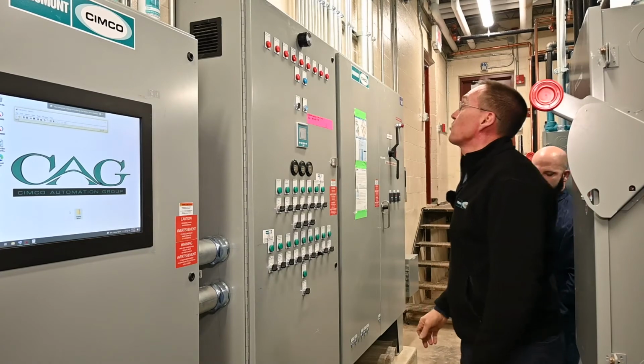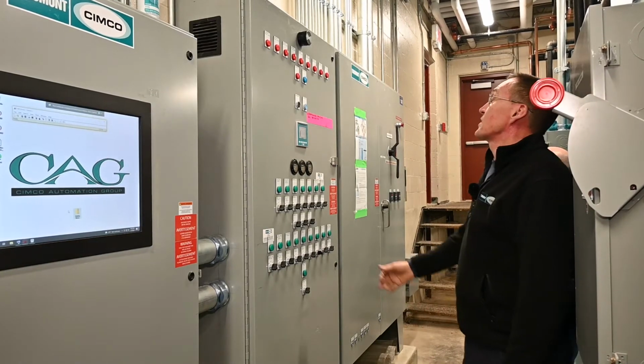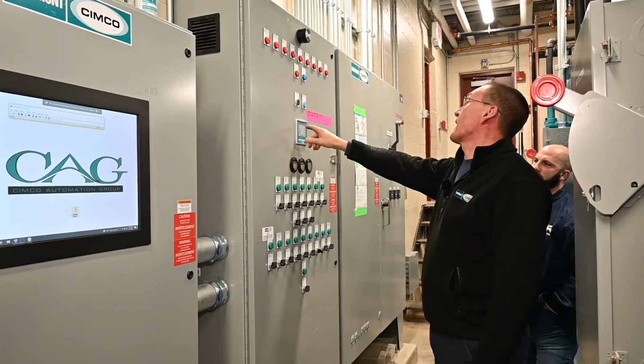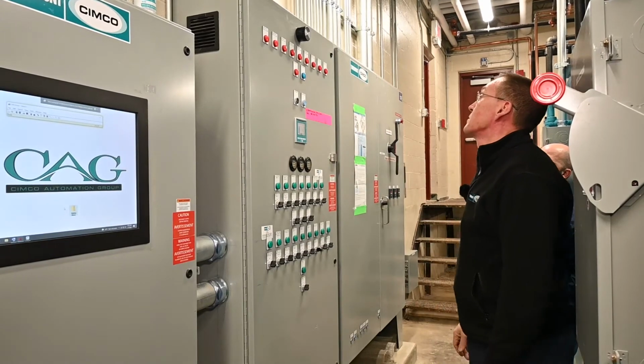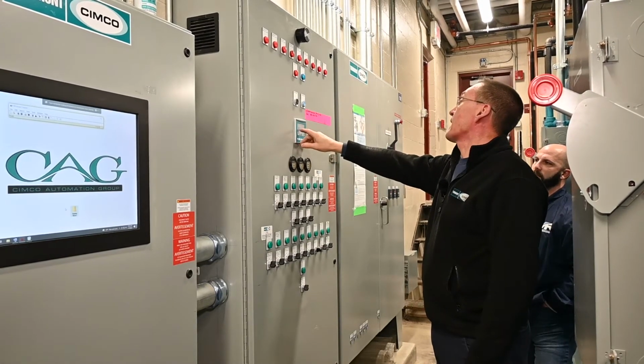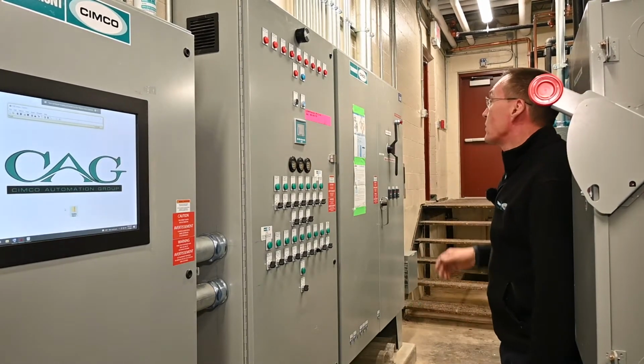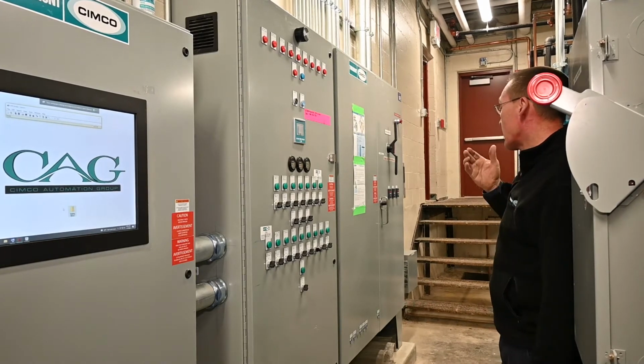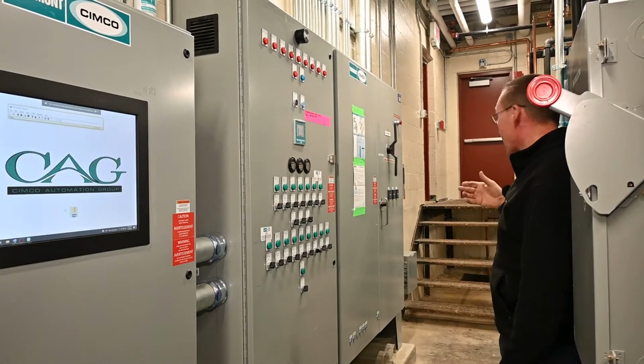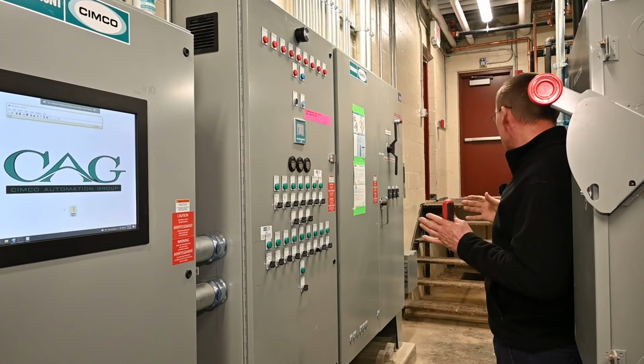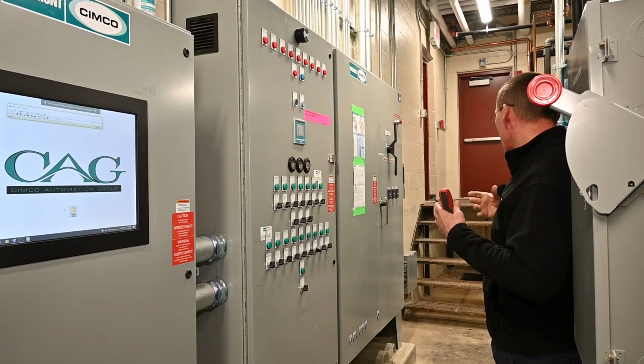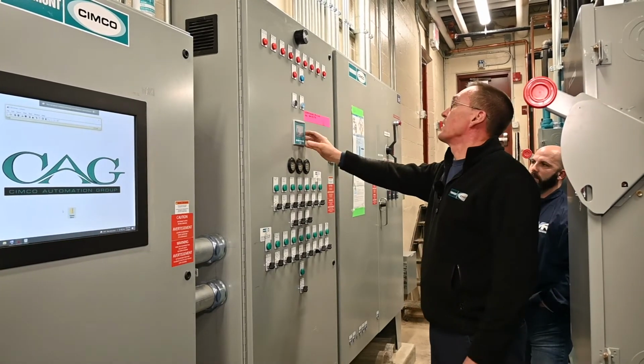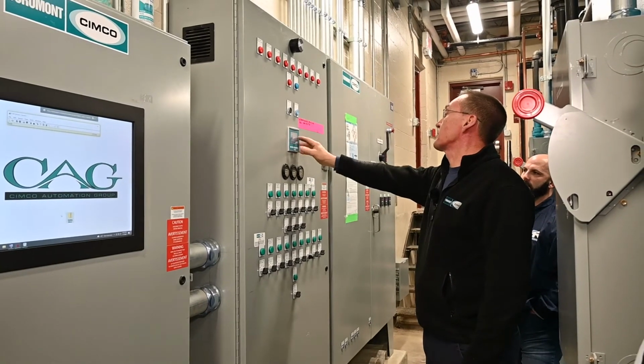You can go to compressor 1 status. That status is going to show you whether or not it has a compressor start, its run status, and anti-cycle. We only allow these compressors to start every 20 minutes. We have to cool the motor windings down and then allow it to start, because we don't want to short something out. And you'll see that anti-cycle light lit here. It'll be orange.